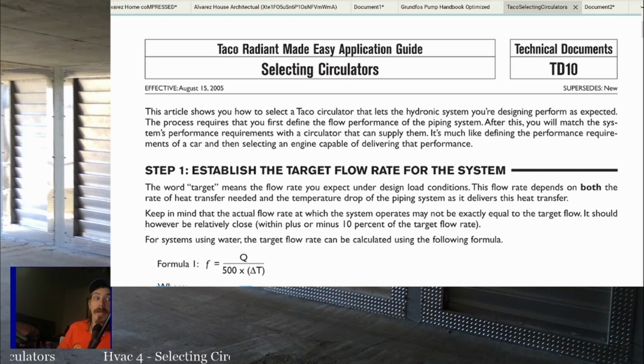And I have run into boiler systems a couple times where they'll complain it's hard to get water to all the radiators, or it takes forever to bleed the air and they can't get everything, it never seems to work right. And sometimes that's just because somebody's replaced a circulator with the wrong kind.